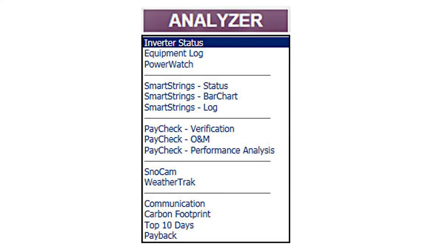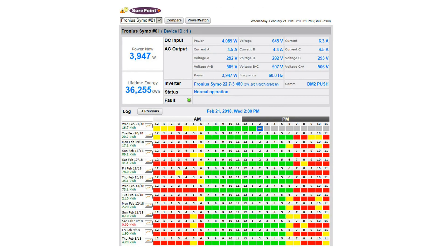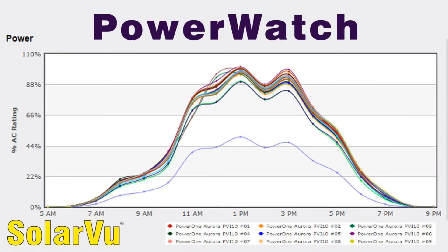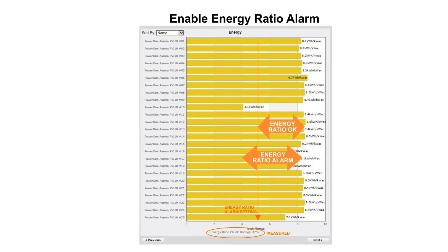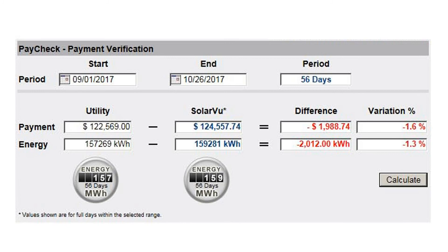SurePoint tools that O&M staff use for troubleshooting include inverter status, a 30-day log of inverter and meter values, PowerWatch which detects low output inverters by comparing them to each other, SmartStrings for finding bad panels, and PayCheck to verify correct utility payments.